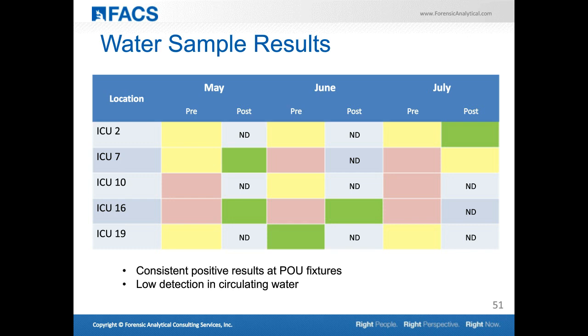You can see some of the results in these rooms. We look at pre- and post-flush samples. Pre-flush samples represent the water coming out of a localized fixture—what people are first exposed to. Post-flush samples are more representative of the circulating water, since we flush it out to the nearest branch, representing the system as a whole rather than a given fixture.